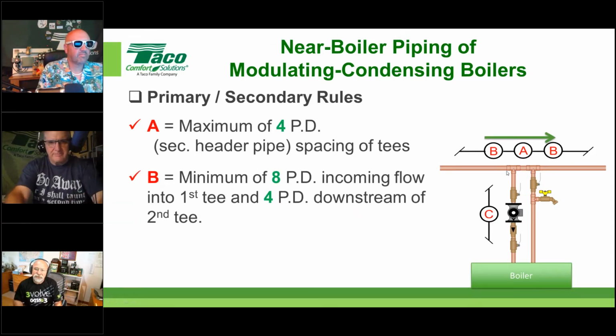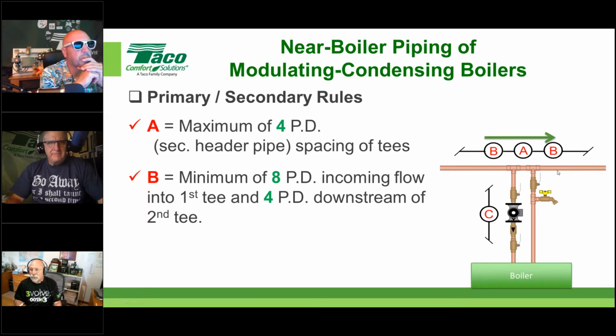Note B says just the opposite of that. As a minimum, I want 8 pipe diameters coming from left to right here, because that's the direction of flow. So I want this to be a minimum of 8 pipe diameters. And once we get past these closely spaced T's here, or the T's that are butted together, then I want at least 4 pipe diameters before anything else happens. And I'll show you on another slide why that is.